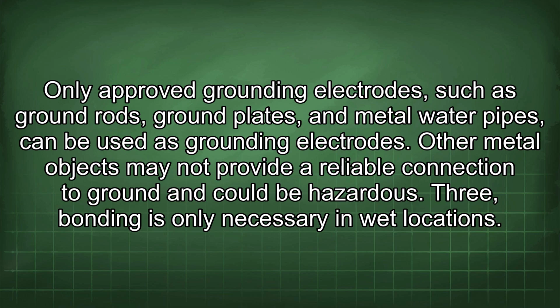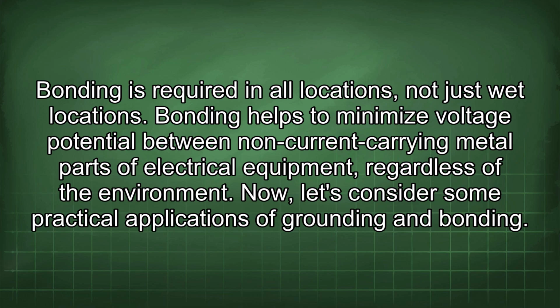3. Bonding is only necessary in wet locations. Bonding is required in all locations, not just wet locations. Bonding helps to minimize voltage potential between non-current carrying metal parts of electrical equipment, regardless of the environment.